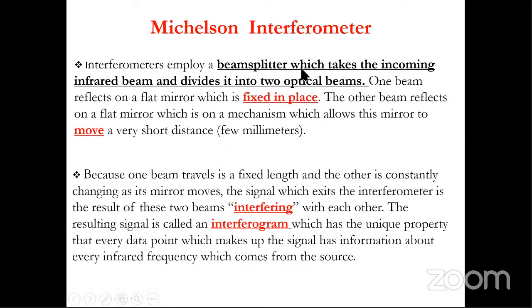In the Michelson interferometer, the beam splitter takes the incoming infrared beam and divides it into two optical beams. One beam reflects from a flat mirror which is fixed in place. The other beam reflects from a flat mirror on a mechanism which allows the mirror to move a very short distance, a few millimeters. Because one beam travels a fixed length and the other is constantly changing as the mirror moves, the signal which exits is the result of the two beams interfering with each other. The resultant signal is called an interferogram, which has the unique property that every data point making up the signal has information about every infrared frequency coming from the source.